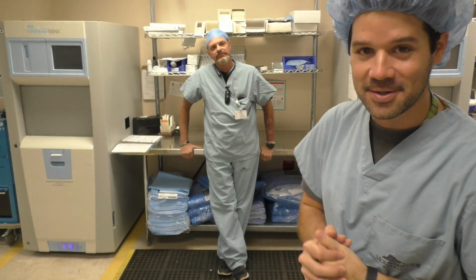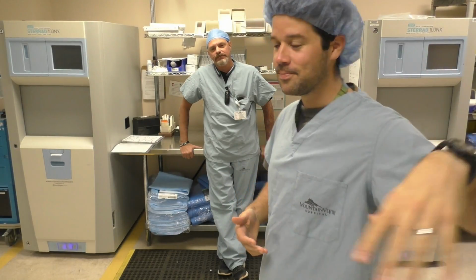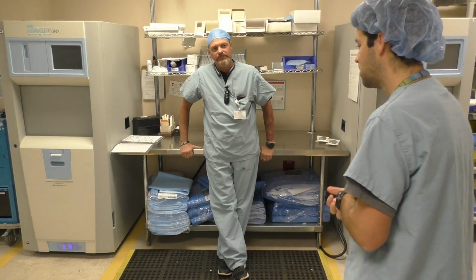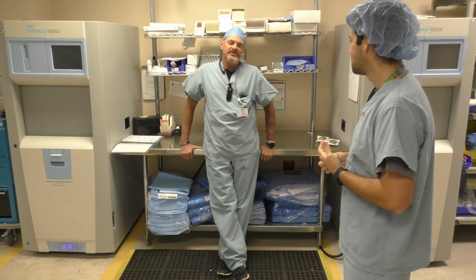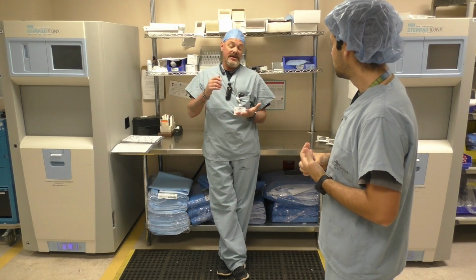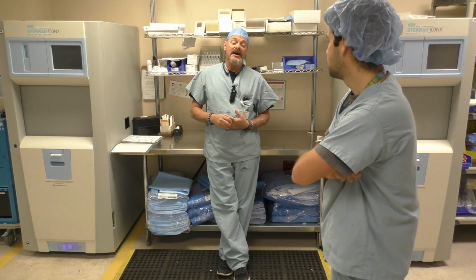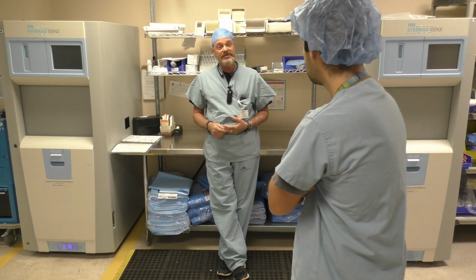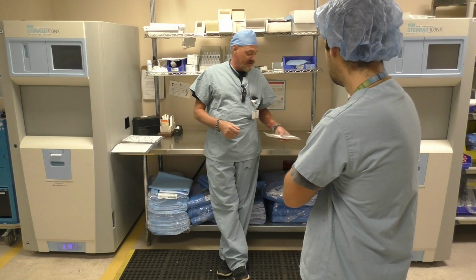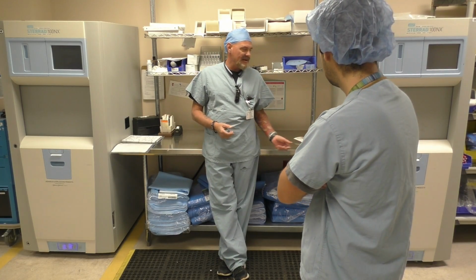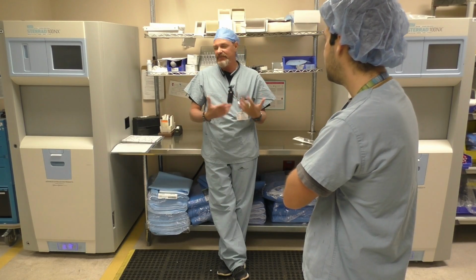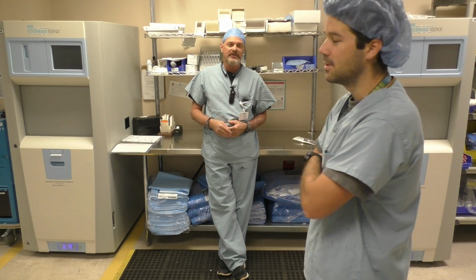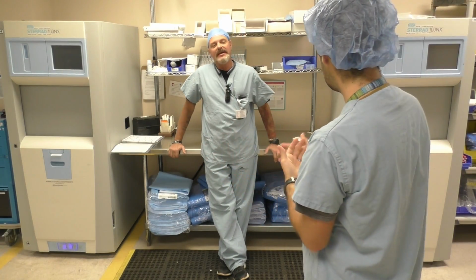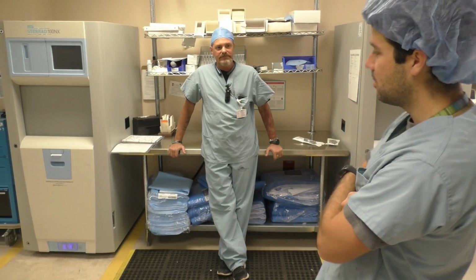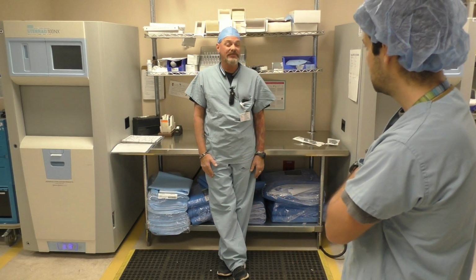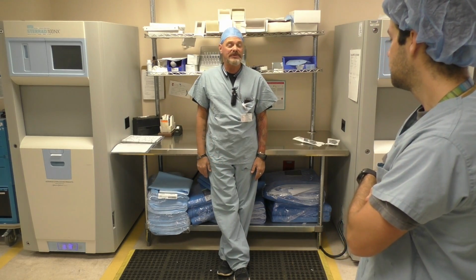Alright, so another form of sterilization, aside from the steam sterilization that we just went through, we have our Sterrads here. You can kind of explain the Sterrads, what they're used for. Sterrads are used for delicate style instruments such as cameras, flexible scopes, some light cords. For an example right here, a Doppler probe. Anything that's delicate that can't withstand high heat inside of the autoclave. Okay. So just think delicate things. Yes. Cords, things with cords, scopes, cameras. Some scopes are steamable. They're autoclavable. It just depends on the brand and what style they are.